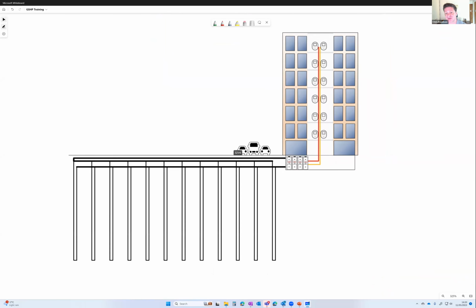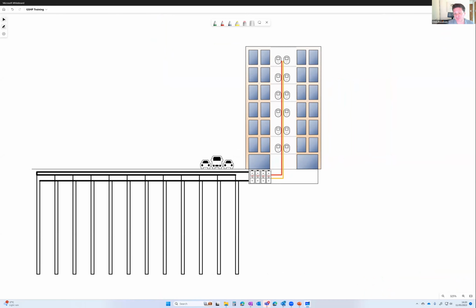So this is a central plant solution ground source system. So we've got heat pumps here down in the basement. We've got highly insulated pipes going up the building. And we've got in the dwellings heat interface units. And those heat interface units will be delivering domestic hot water into the dwelling and also space heating. Now, domestic hot water, we could be looking for something around the 65 degrees in that domestic hot water. In space heating, we could be doing that maybe as low as 35 degrees C. But because we've only got one network, and because we've got to deliver that 65 degrees, we've got to run that whole network at 65 degrees all the time.